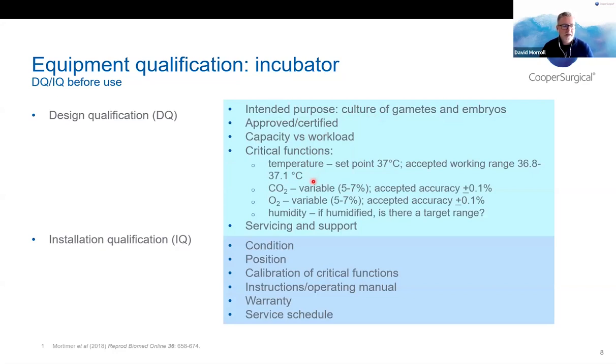And then the installation qualification is about where we're putting it, making sure it's arrived and is installed in good condition, that it's appropriately calibrated, that we've got an operating manual. And of course, people need to read that operating manual and know how to use pieces of equipment. And we'll also want the backup elements, so the guarantees, the warranties, the service schedule, and so on.